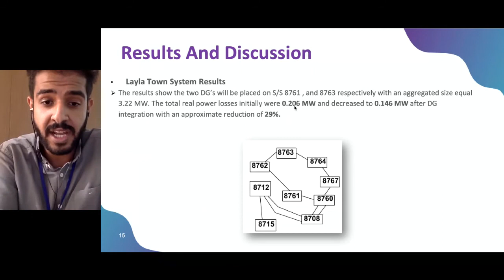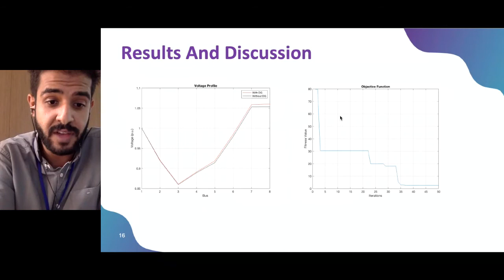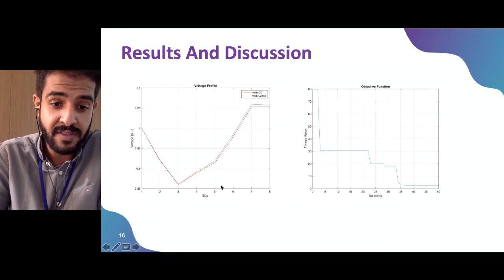For Layla Town, the same code was tested on the Layla Town network, and the distributed generation is optimally placed on substations 8761 and 8763, here on this diagram, with a total size of PV distributed generation of 3.22 megawatt. And it has been noticed that the real power losses reduced from 0.206 megawatt to 0.146 megawatt, a reduction of around 29% of the whole system real power losses. Also here we can notice the improvement in voltage profile, especially on the buses where the PV distributed generation is installed, which are 5 and 7.